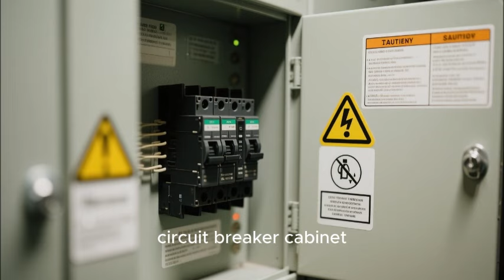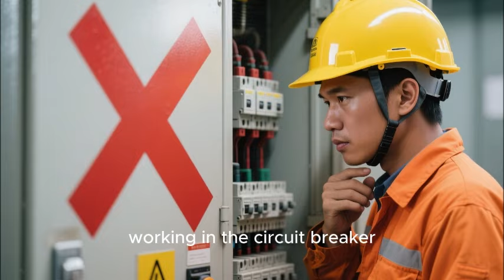When working at an energized circuit breaker cabinet, what safety measures must be taken? Answer: do not allow working in a circuit breaker compartment if the upper or lower jaw is still energized. The circuit breaker cabinet door must be closed and locked after pulling the circuit breaker out. Hang a sign: no entry. High voltage is dangerous and fatal, on both the front and back of the circuit breaker cabinet.